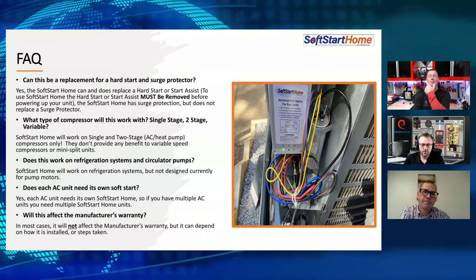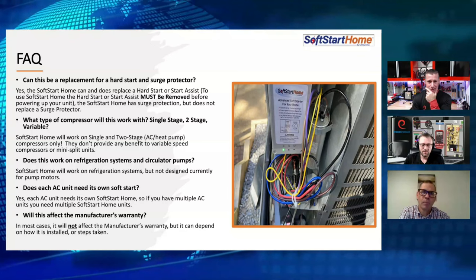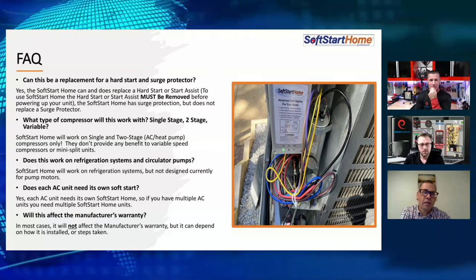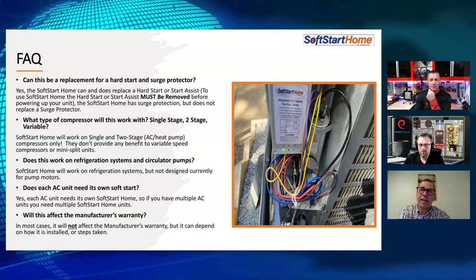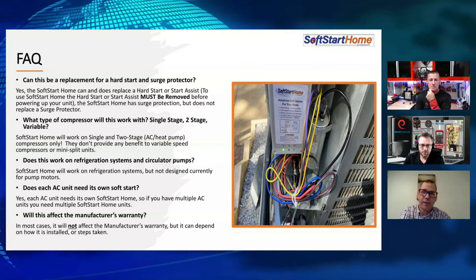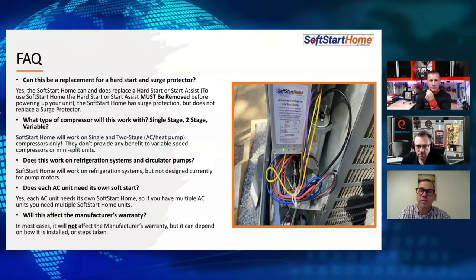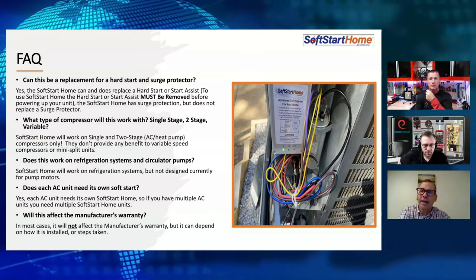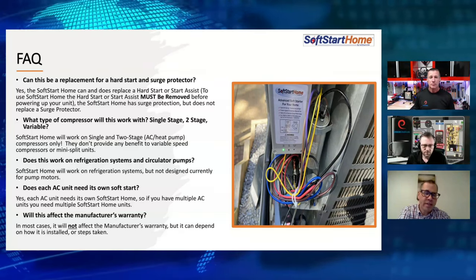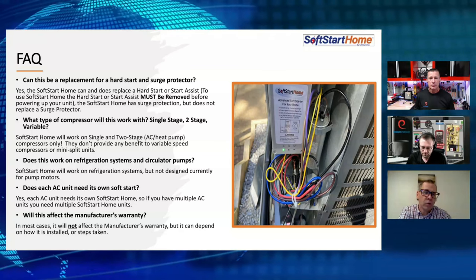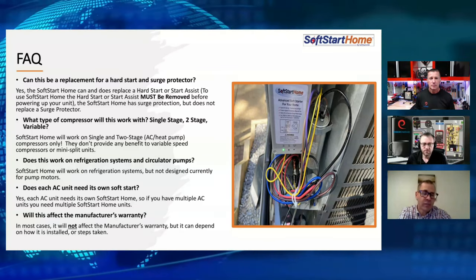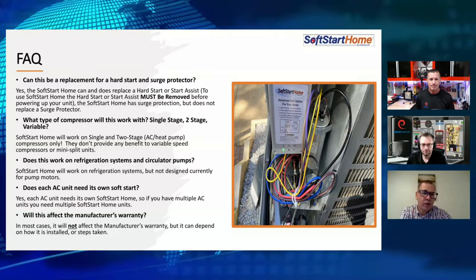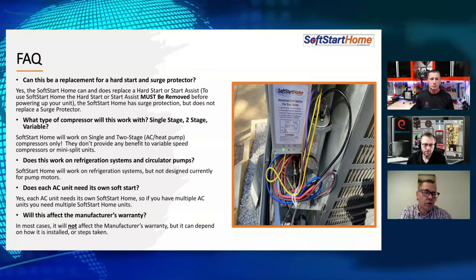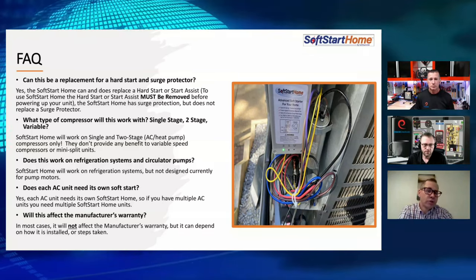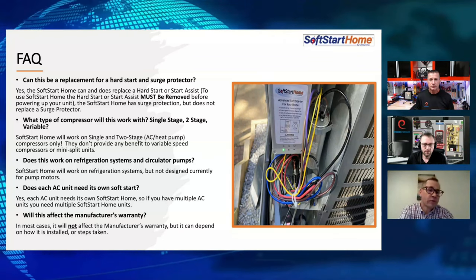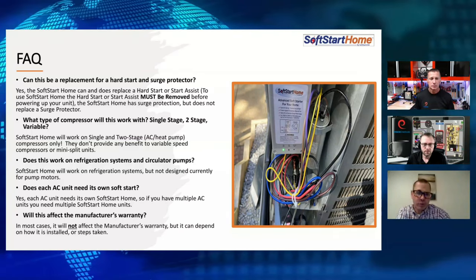Good question: can it be a replacement for a hard start and surge protector? The answer is yes, it can definitely be a replacement for a hard start or start assist. As far as surge protection, these are typically put on units that aren't inverter based and don't have a lot of control boards, so surge protection often isn't used there. We would never say we're a replacement for surge protection, but we do have surge protection built into our unit.